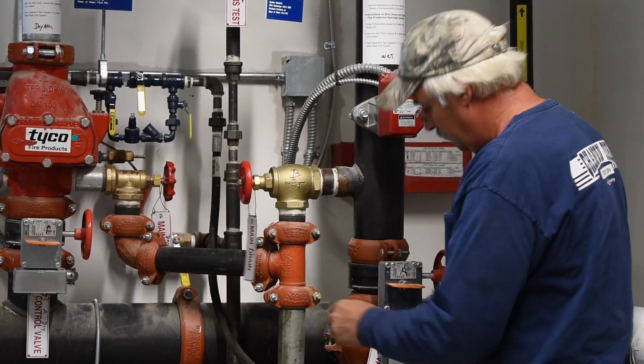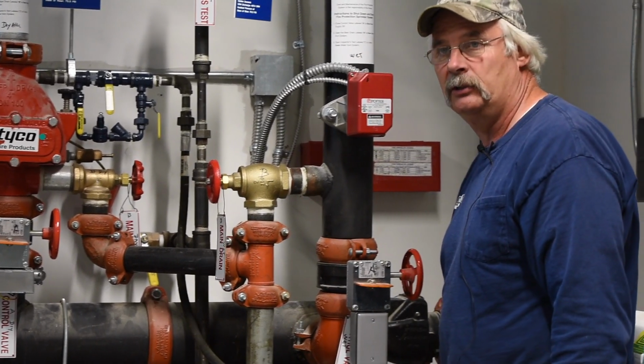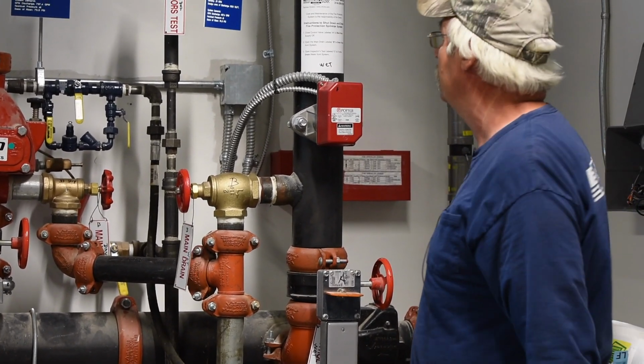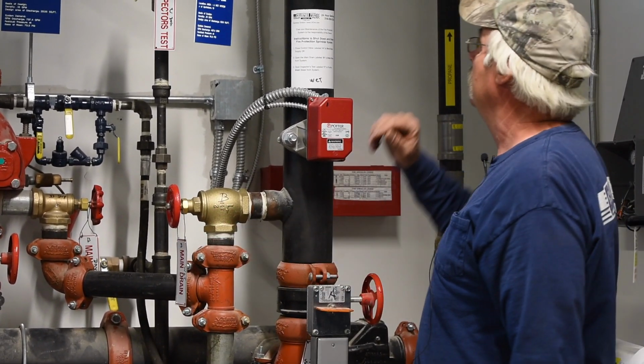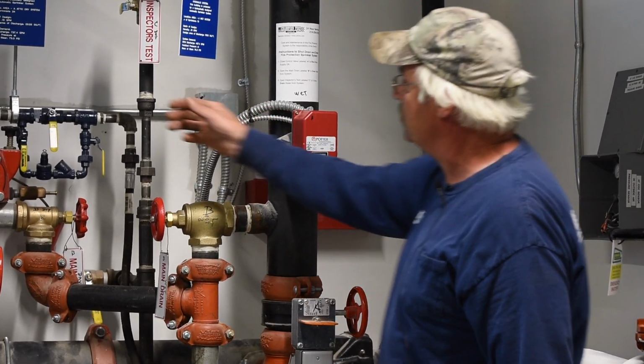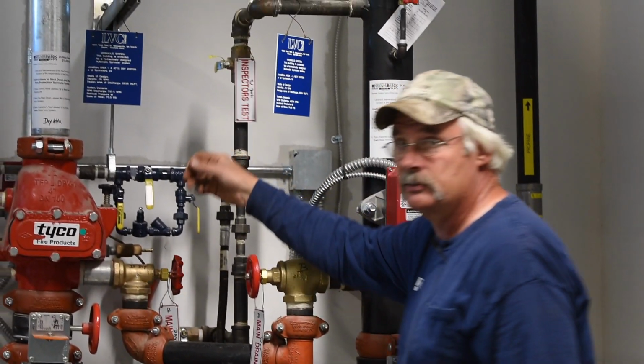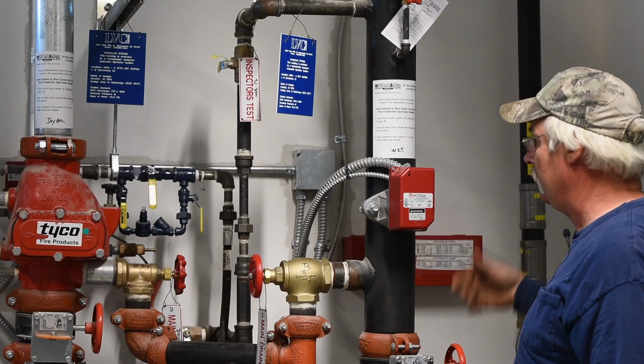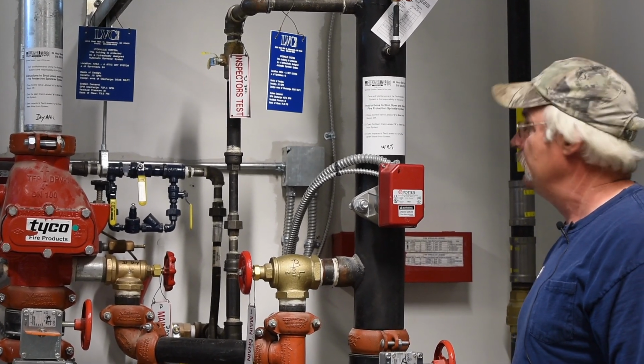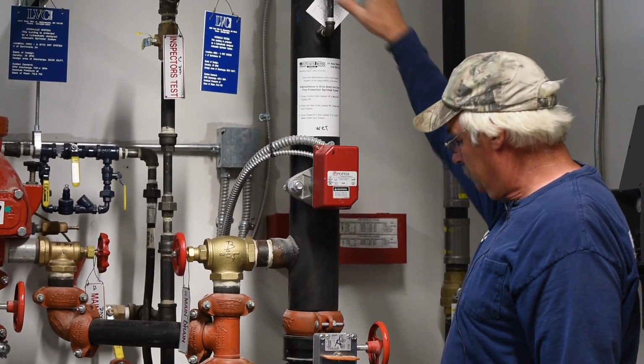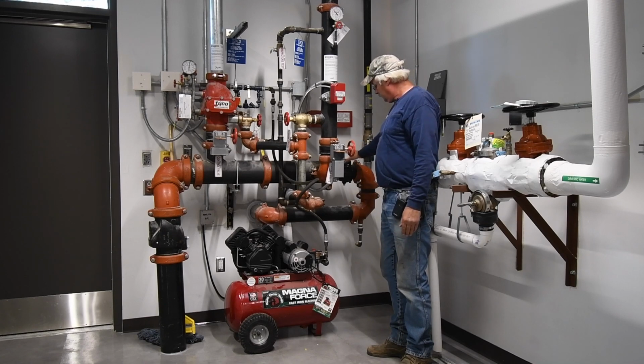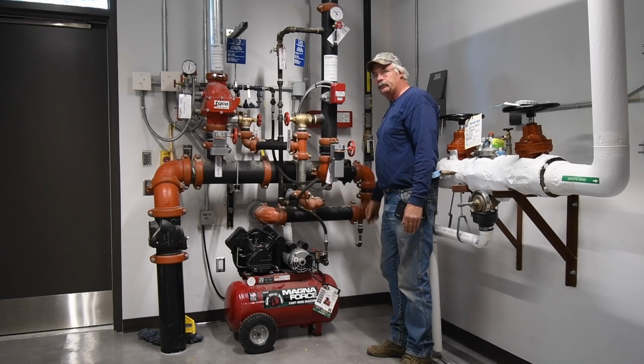Open this up. It goes down the outside of the building. So it all drains outside. Same as the dry. Step three, open inspector's test C, which is right here, inspector's test wet C. And that also is piped outside. Water gauge is right here. Control valve here. Fire department connection comes in.